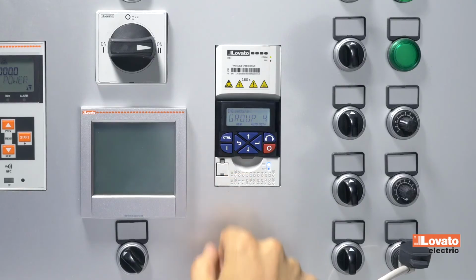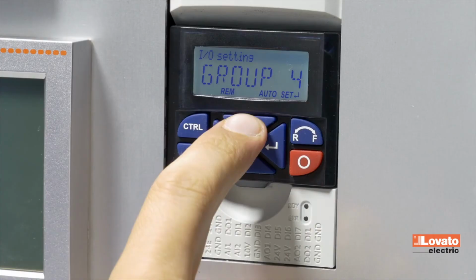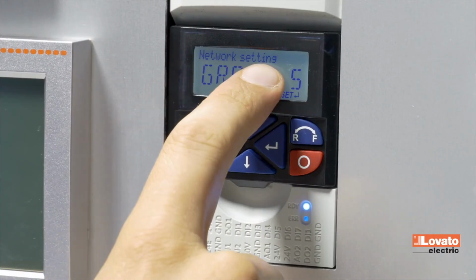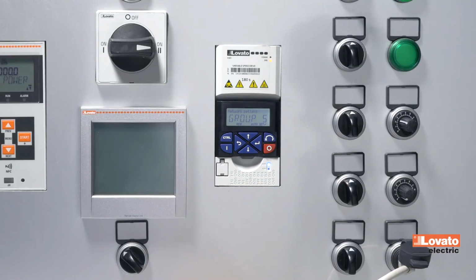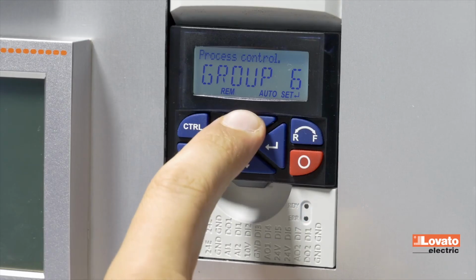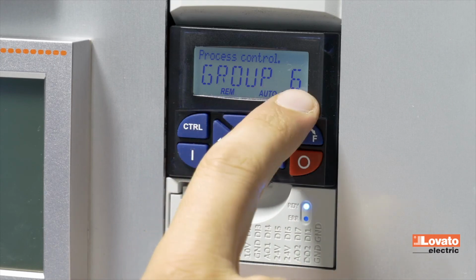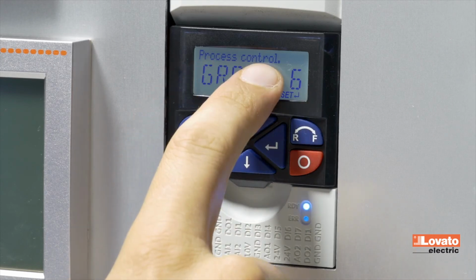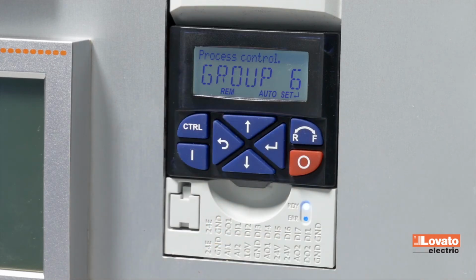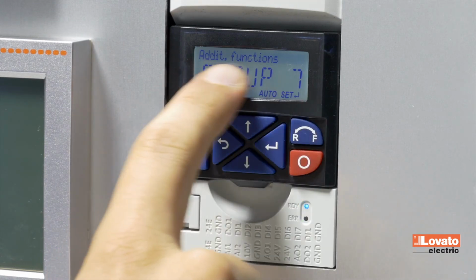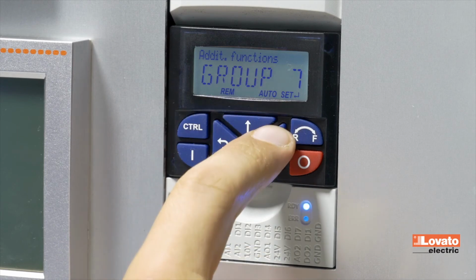Group 5 is used to set the parameters of the communication bus, Modbus, CAN-Open, Profibus, depending on the type of logic unit mounted on the drive. Group 6 is the menu to enable PID control and to set its parameters. Group 7 is used to configure advanced functions.